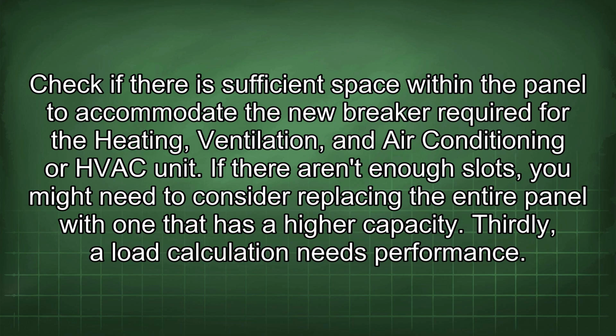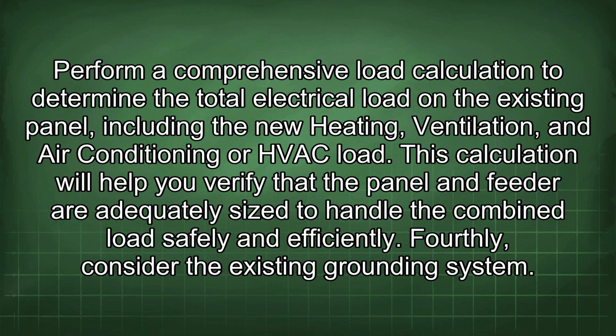If there aren't enough slots, you might need to consider replacing the entire panel with one that has a higher capacity. Thirdly, a load calculation needs to be performed. Perform a comprehensive load calculation to determine the total electrical load on the existing panel, including the new heating, ventilation, and air conditioning, or HVAC, load. This calculation will help you verify that the panel and feeder are adequately sized to handle the combined load safely and efficiently. Fourthly, consider the existing grounding system.